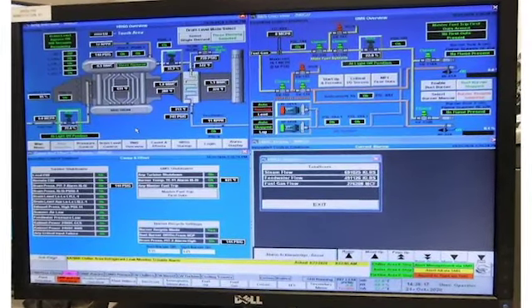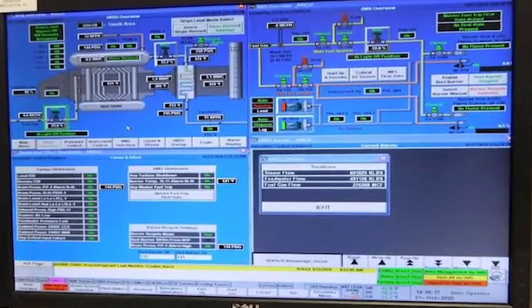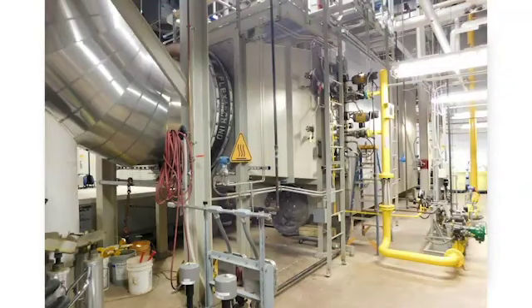It's a water tube boiler with a generator bank in the back and a very large economizer, which improves its overall efficiency. A shot here of the duct burner, which is the bread and butter of this whole setup. The duct burner brings in an interesting situation where every BTU that we bring in as gas is actually converted to steam. Okay, super high efficiency once we bring that duct burner on.